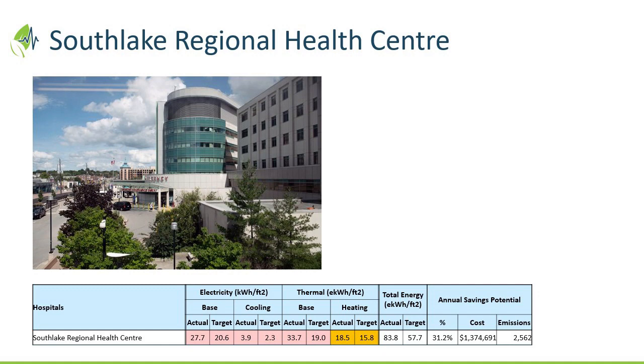Where you see Base Electric, for example, they're using 27.7 kilowatt hours per square foot per year. A target for an acute care hospital of that nature is 20.6. So that's the savings target, which is fan power and lighting and all the other things that they plan to do. The cooling electricity is the extra use in the summer. Base thermal is the year-round gas consumption, which is the biggest single opportunity. And that speaks to the boiler plant, right? So a lot of that is reheat in the air handling systems, which is the load, but it's how the boiler plant runs through the summer, and the extra heat in the winter actually is not that unreasonable, and we'll talk some more about that.